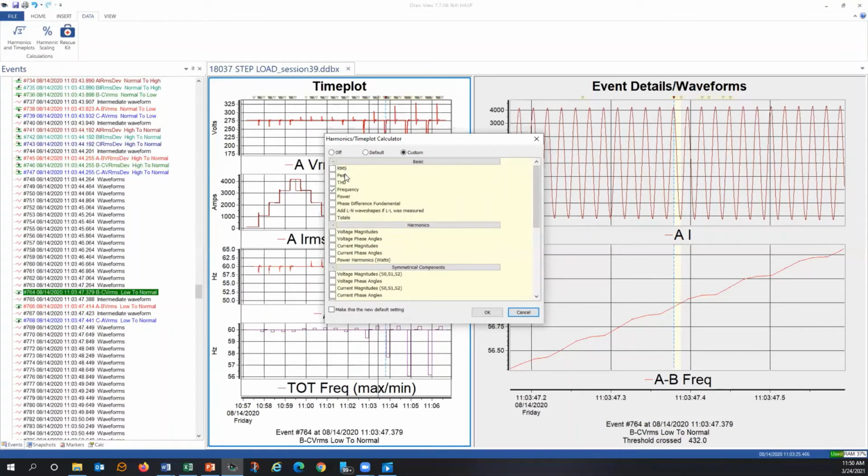So you have RMS, peak, THD, frequency, power, phase information, totals. So these are things that could be computed or recomputed, to the point in one of the chats we had before, if it's already in the instrument database. We're not saying that you need to recompute information, but there are applications where that may become beneficial to you. So one may be computing THD from wave shapes that have been recorded. All right, maybe you just want to do cycle by cycle THD. Again, THD for the instrument is going to be on a 200 millisecond window average. So these are different applications. Only you folks would know how to best apply this for your particular application. We can certainly make suggestions for you, but this is just in general how this works.